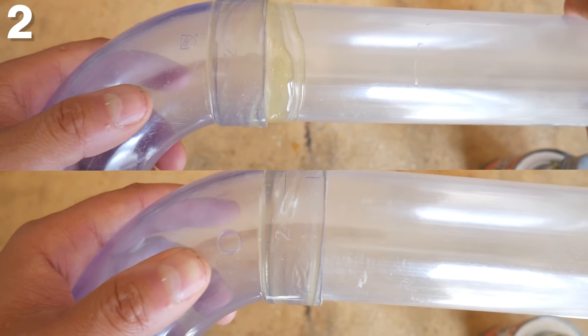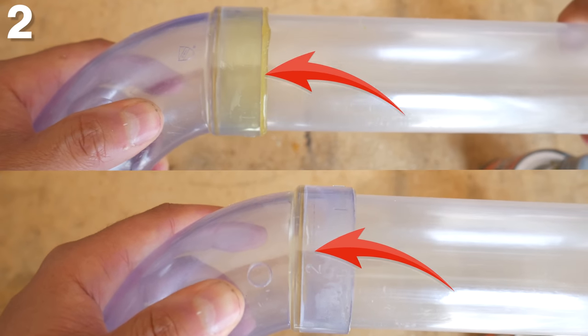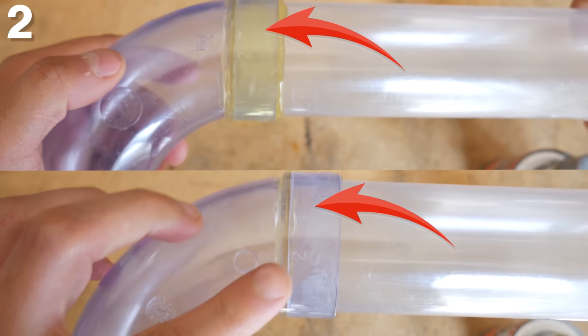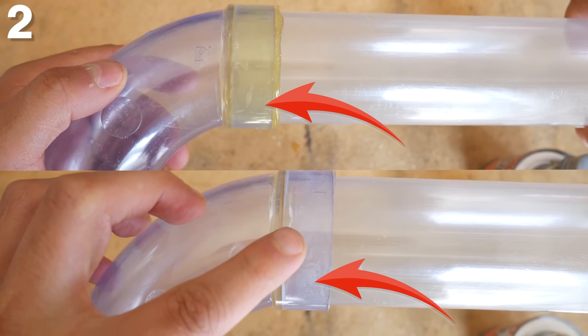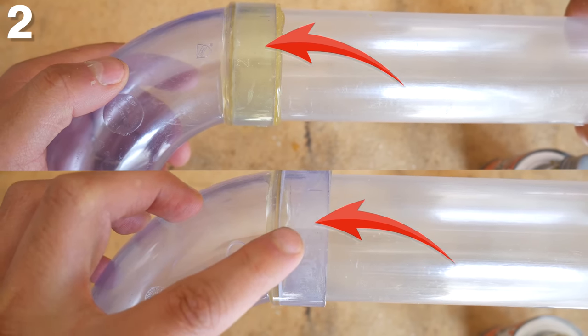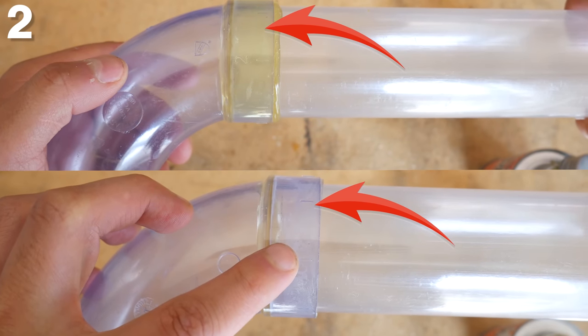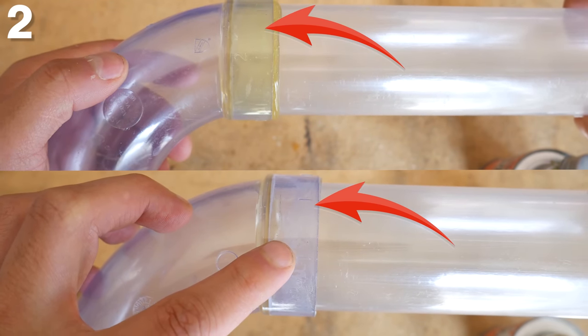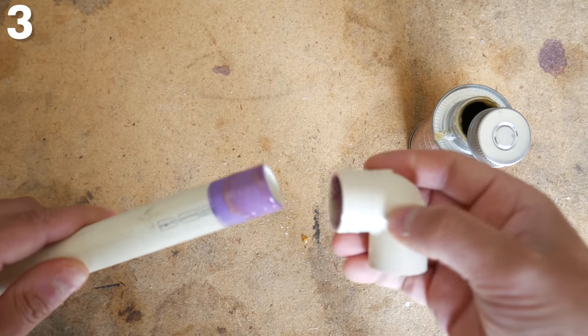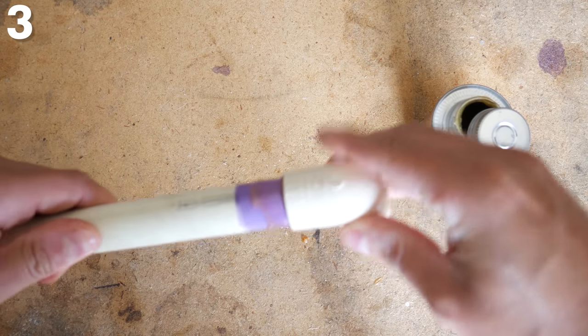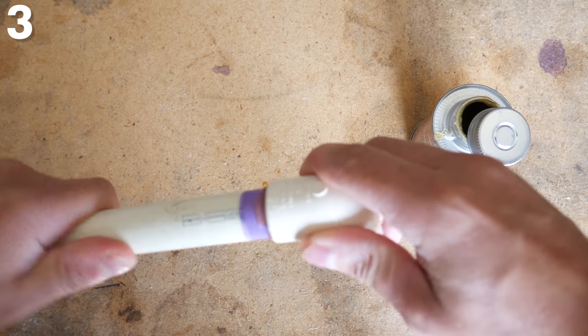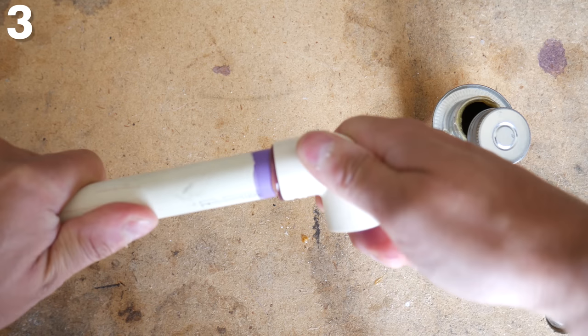Here are two clips I shot of a clear setup. The top one only has glue in the fitting and the bottom one has glue on both. As they're inserted, you could clearly see that not applying it on both results in a dry spot. Something else that helps getting full coverage is to turn the pipe or fitting a quarter turn just to make sure it gets proper coverage.